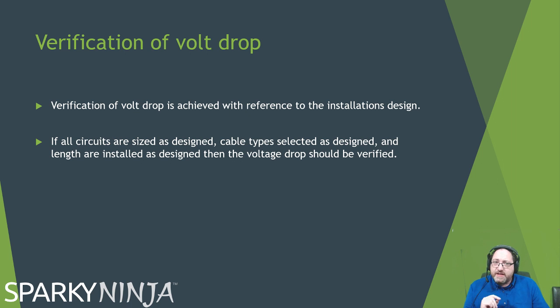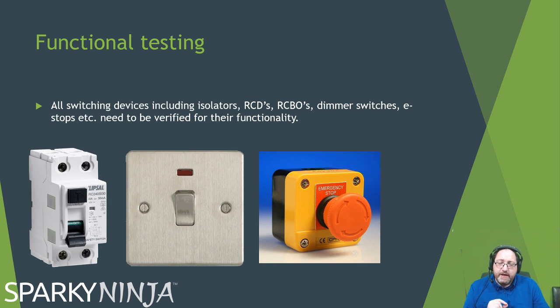Okay, and the last thing you're going to check is the functionality. So once you've got the rig and you've done all this, you've done your RCDs, you're then going to trip out your RCDs. You can go main switch, MCBs, anything else that's there that's an operational, functional operating device. Do it, because you need to know it works before you actually then say yes, that's free to use, go on and use it.